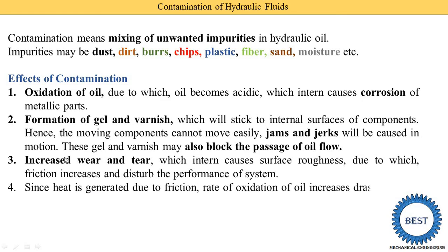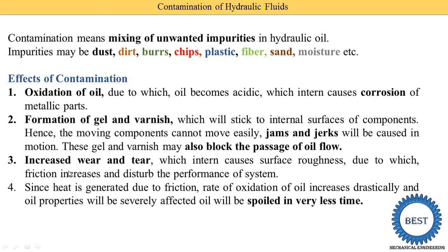Due to increased friction, more heat is generated and the temperature rises significantly. This high temperature drastically increases the rate of oxidation of the oil, severely affecting oil properties. The oil is spoiled in a very short time, meaning oil life is reduced and oil needs to be changed frequently.